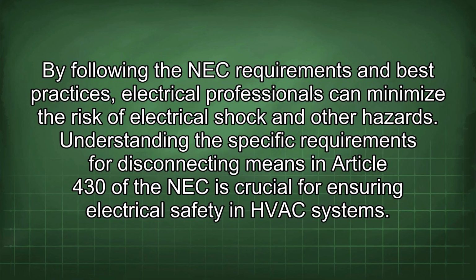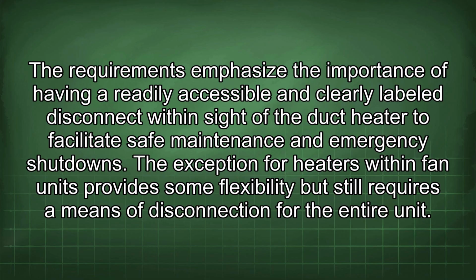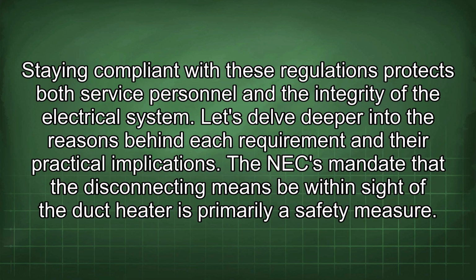Understanding the specific requirements for disconnecting means in Article 430 of the NEC is crucial for ensuring electrical safety in HVAC systems. The requirements emphasize the importance of having a readily accessible and clearly labeled disconnect within sight of the duct heater to facilitate safe maintenance and emergency shutdowns. The exception for heaters within fan units provides some flexibility but still requires a means of disconnection for the entire unit. Staying compliant with these regulations protects both service personnel and the integrity of the electrical system. Let's delve deeper into the reasons behind each requirement and their practical implications.